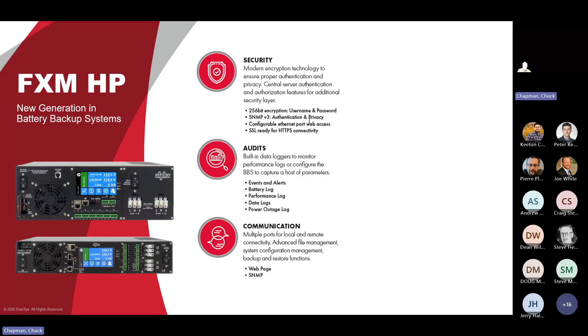You can configure alarms, configure the ports as I was just discussing, and set timers. You can say you don't want to indicate anything for 15 minutes after the inverter goes on standby, unless the batteries are at less than 60%. You can put together very complicated go, no-go statements into a script, and it will follow that and open and close dry contacts as needed.